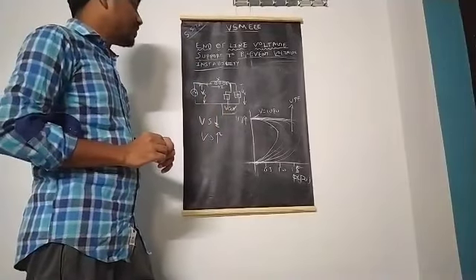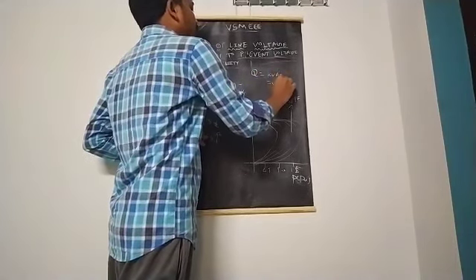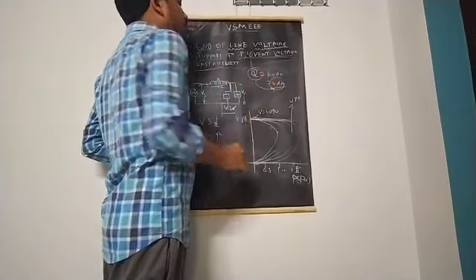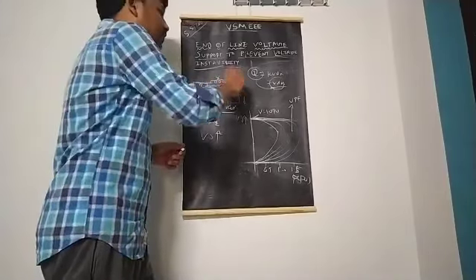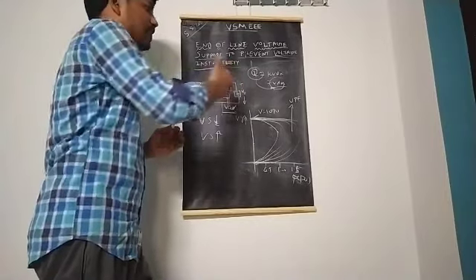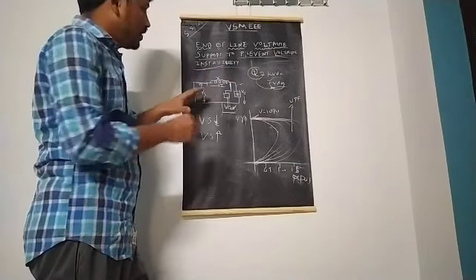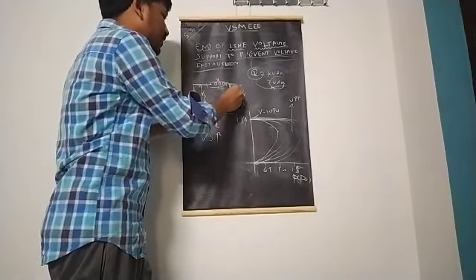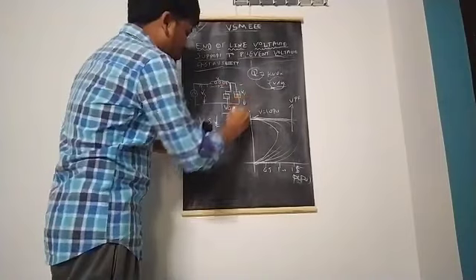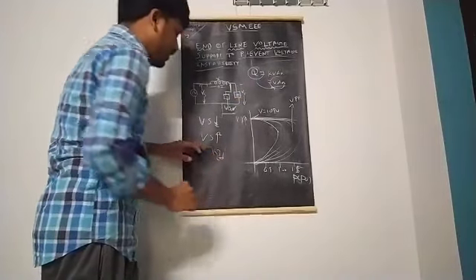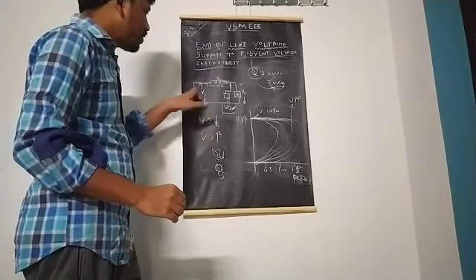This is nothing but a VAR compensator — in our topic, that is the reactive power compensation device. Because the unit of reactive power Q is KVAr or VAR, that's why the reactive power compensation device is named the VAR compensator. Here, we are using the shunt compensation device to mitigate the voltage drops in the loads, and to reduce the voltage drop from the VAR compensator devices. While we are connecting the voltage compensation devices, it supports the reactive power, and therefore it meets the demand of the load.